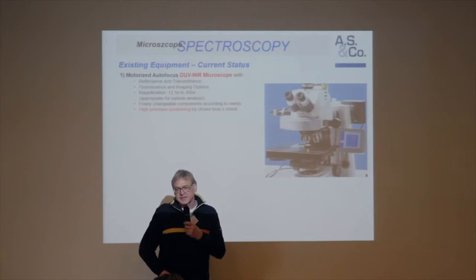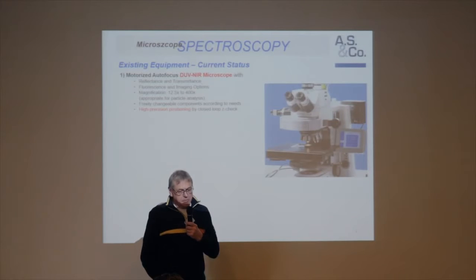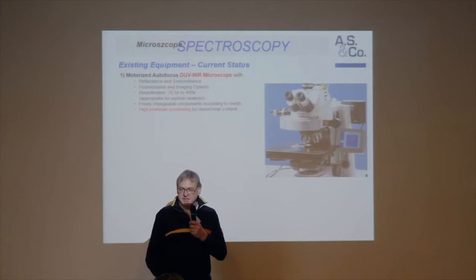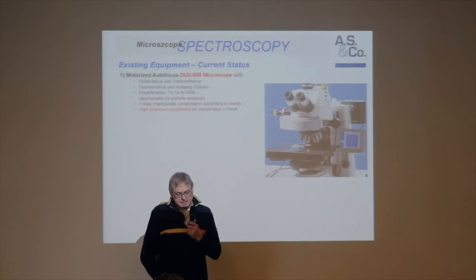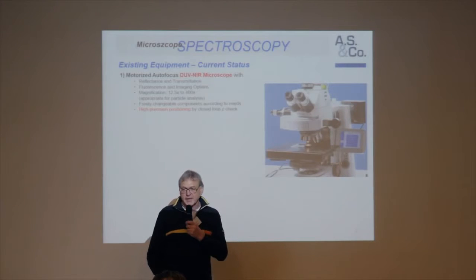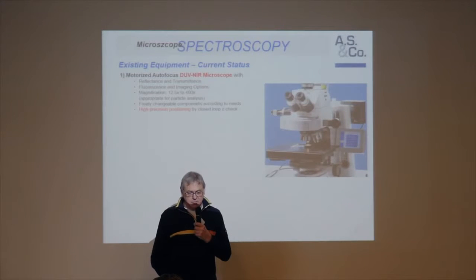The current status is we have manual microscopes and of course motorized microscopes. Motorized microscopes have millions of options and we need some of them which make our life easier: motorized field stops, focus, stray light reduction, and all these things. We use this in a standard microscope and we modify these microscopes to deep UV as well as to infrared, so the microscopes we design for the forensic group are able to measure 200 to 2000 nanometers and are scaled to different applications.